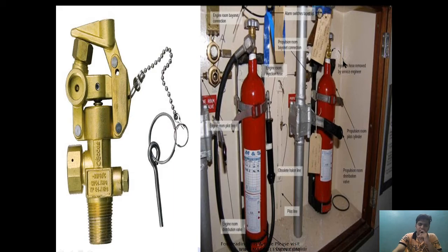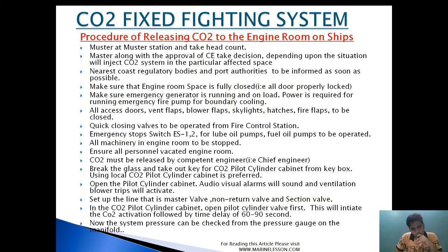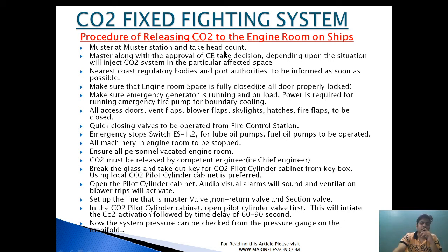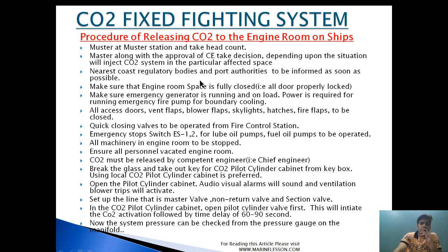Procedure for releasing CO2 to the engine room on a ship: First and foremost, muster all personnel at the muster station and take a headcount to ensure every person is accounted for. After that, the master, along with the approval of the chief engineer, takes a decision depending upon the situation whether to inject CO2 into the particular area. The master gives approval, but the decision and operation will be carried out by the chief engineer. The nearest coast guard, regulatory body, and port authority must be informed.